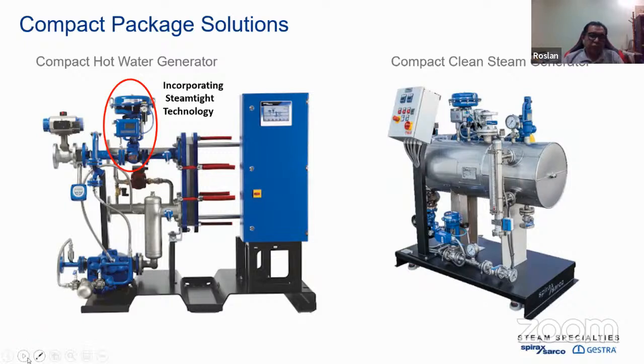For example, if you use this for a hotel or hospital, there are many times, non-peak time, when people are not using hot water. So when there's low demand, the heating requirement is also low, and this valve is required to shut completely. But a normal control valve will somehow leak steam because the method used is metal-to-metal seating, and the best you can achieve with that is class 4 leakage rate. If you want better, you have to spend more.